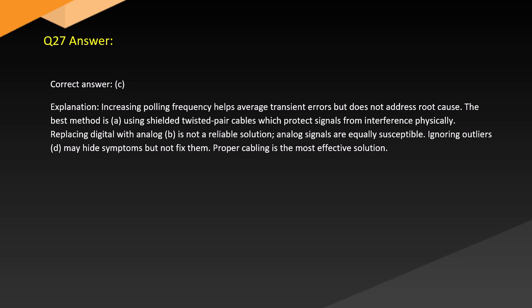Answer. Correct answer: C. Explanation: Increasing polling frequency helps average transient errors but does not address the root cause. The best method is A, using shielded twisted pair cables, which protect signals from interference physically. Replacing digital with analog, B, is not a reliable solution. Analog signals are equally susceptible. Ignoring outliers, D, may hide symptoms but not fix them. Proper cabling is the most effective solution.